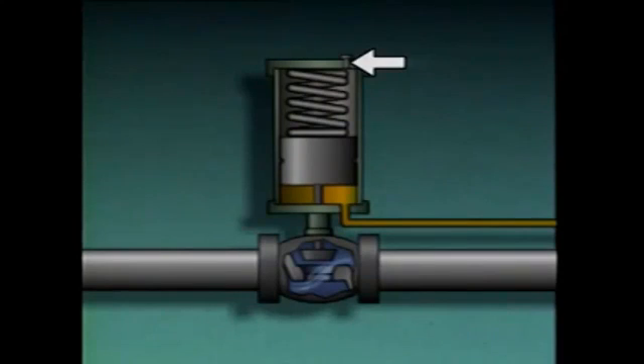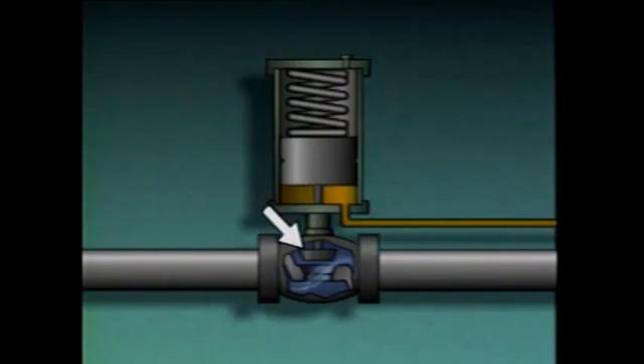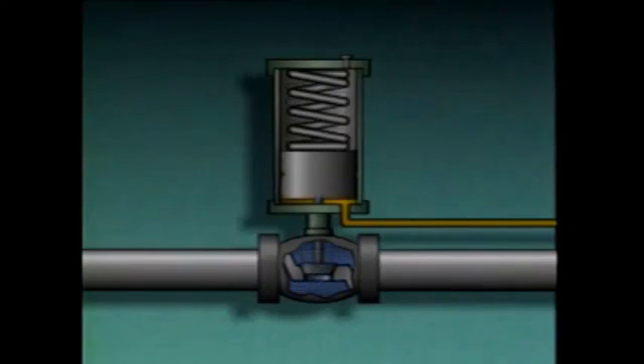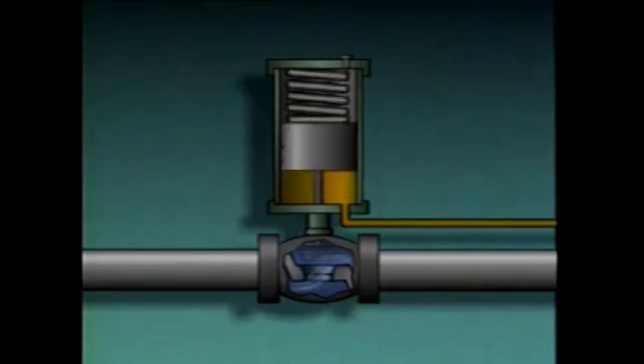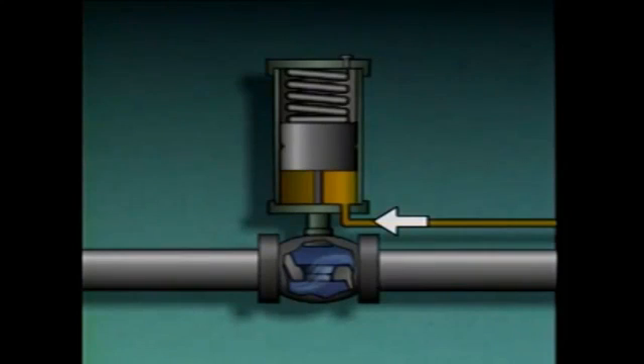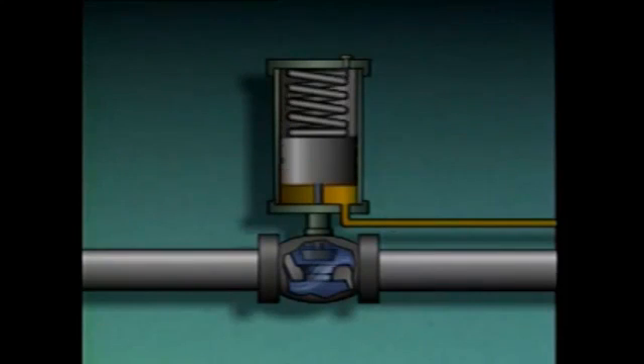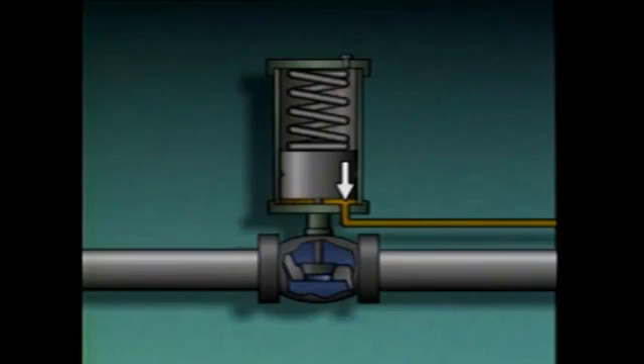A hydraulic actuator consists of a cylinder, a fluid port at the base, a vent, a spring, a piston, and a piston rod connected to the valve disc. When there is no fluid pressure against the piston, the spring keeps the piston at its lowest position and the valve is closed. When fluid flows through the port into the cylinder, the piston moves upward, compresses the spring, and opens the valve. Air above the piston is exhausted through the vent. When fluid flow stops, fluid pressure and the spring hold the piston and valve at their new positions.